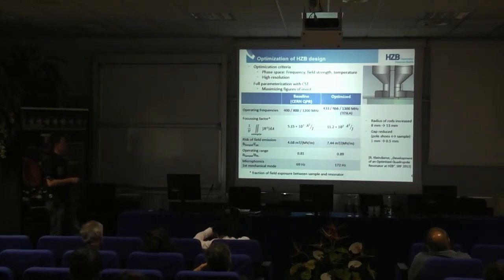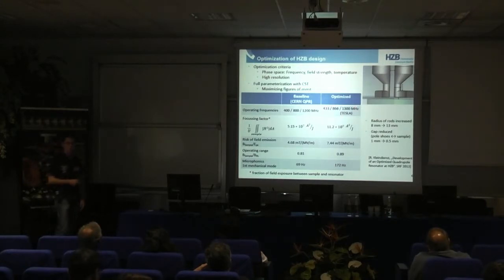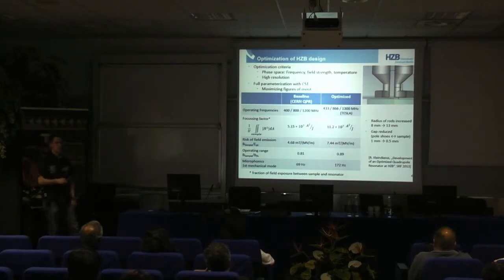We have a base frequency of 433 megahertz and can go up to 1.3 gigahertz, which is the commonly used TESLA frequency. The focusing of the magnetic fields on top of the sample has been increased, reducing the electric field at the sample. This has increased the operating range.